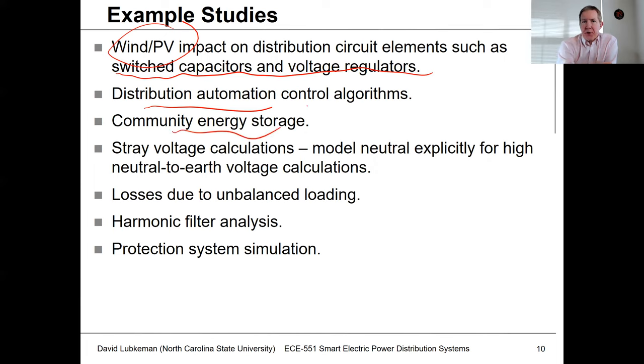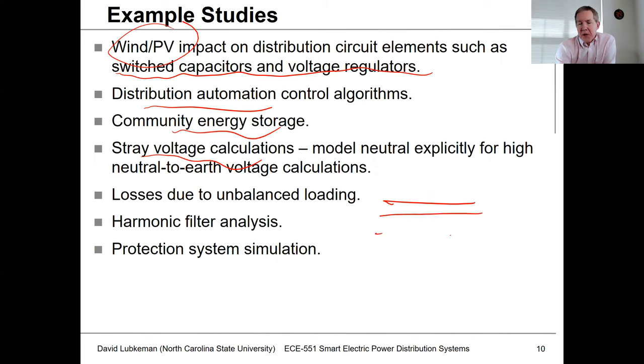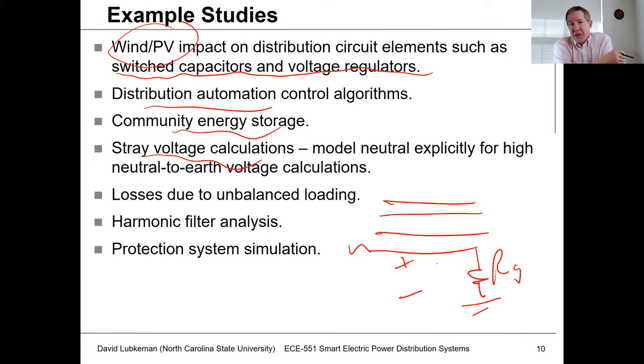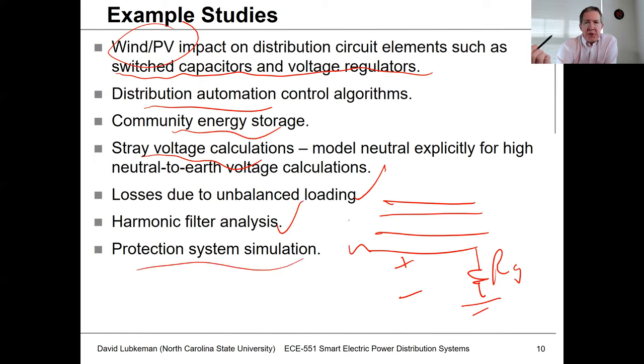OpenDSS was originally developed for wind and PV impact studies on distribution. Through scripting, you can model distribution automation like automated switching schemes, energy storage with custom charge/discharge control algorithms, and stray voltage calculations where a neutral wire has high impedance to earth ground — a characteristic problem in agricultural systems where you may not have good neutral-to-earth ground ties. You can look at unbalanced conditions, harmonic filters, and simulate protection systems. Essentially, through scripting you can customize the engine to simulate almost anything.